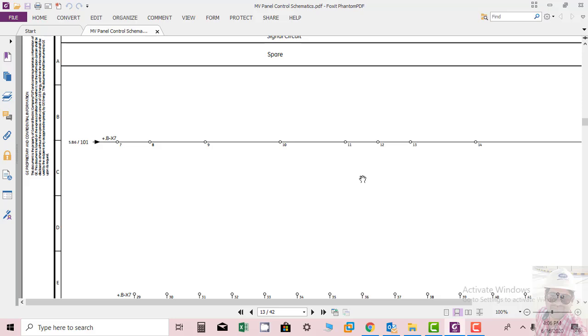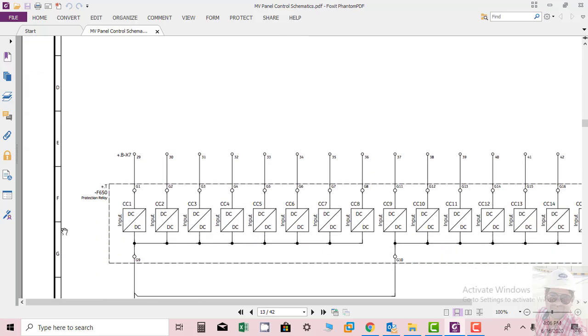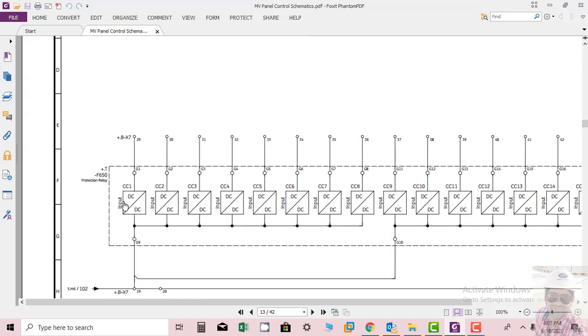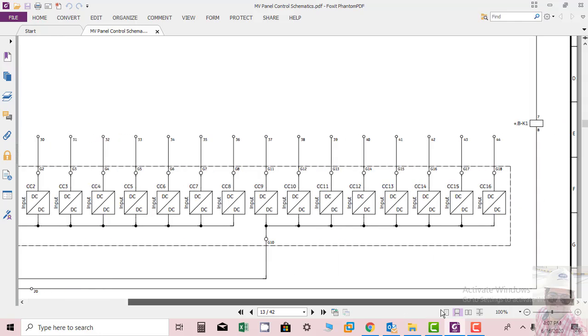These are all the spare binary inputs of F650, and these spare binary inputs are also wired up to the terminal block. So if there is a requirement at site to connect any spare input, it can be connected to spare inputs that are already available up to the terminal block.